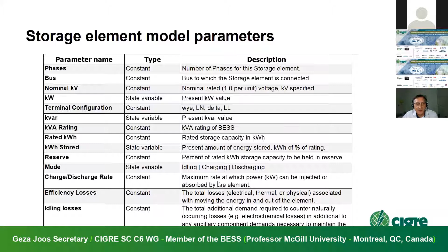This is a list of the parameters of the battery energy storage system. I will not go through this. Now, the operating mode, I did mention some of them, the intelligent functions. The other thing is that the battery energy storage, like any wind turbine generator or solar system, is typically synchronized to the grid using a PLL. Then you can operate in grid following mode, which is the typical mode of operation for solar and wind, which is PQ controlled injection.